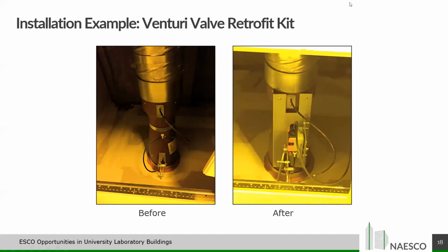Thanks, Paul. So yes, this is a valve retrofit, and this is basically what we're doing to the lab space with the existing infrastructure. The picture to your left is a Venturi valve, constant volume, and the picture to the right is the after retrofit with an electric actuator. Now, how we basically do that is we end up installing a base plate and the electric actuator, which then will get wired to a controller. And again, based on sash position, it'll adjust accordingly to ensure that safe conditions exist for that user when in front of the hood.